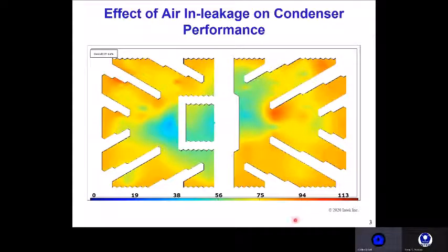This first example is from a power generation facility that we worked with to identify the source of their poor condenser performance. It started with measuring the level of air in-leakage using the Intek REEvac condenser monitor. In analyzing the performance data we gathered from the REEvac, we recognized that there were other factors affecting the performance that needed to be understood. One of these was the condenser cleanliness factor.